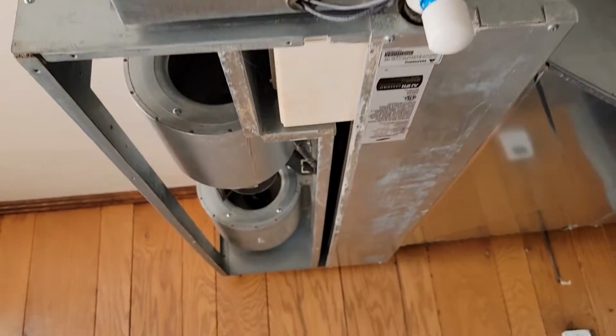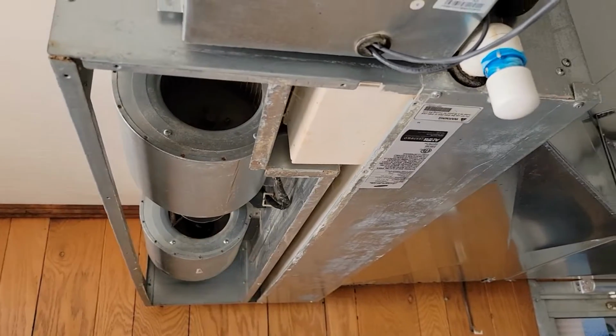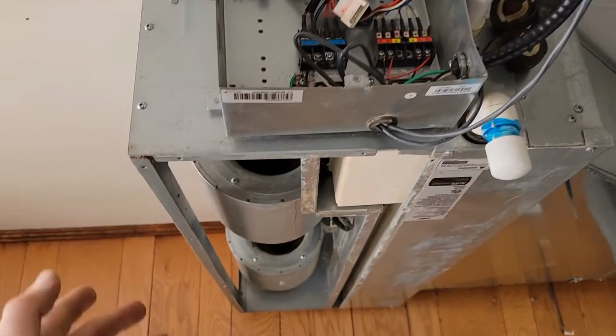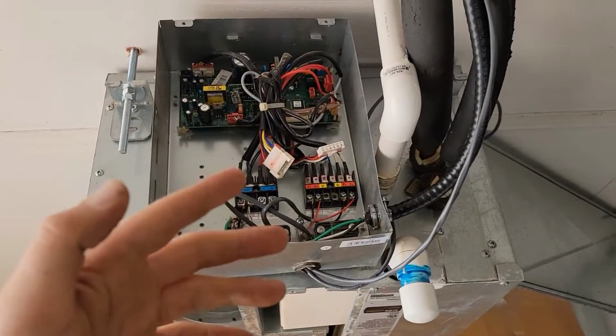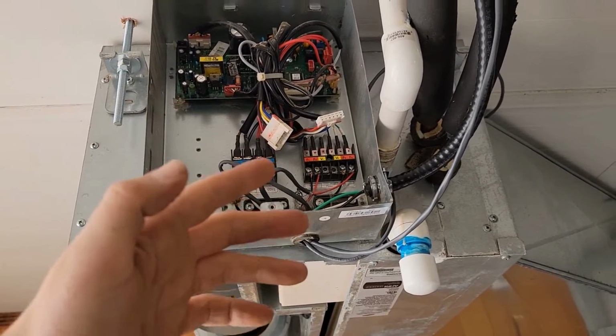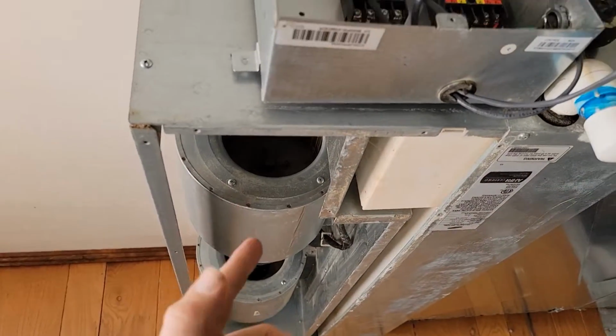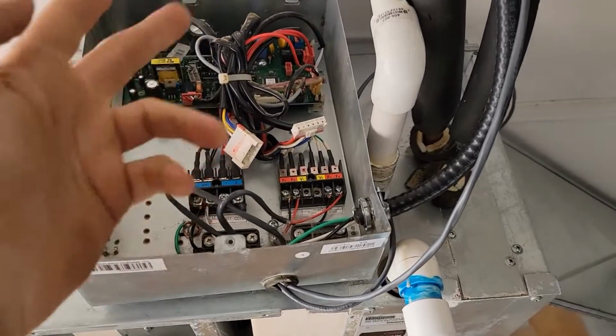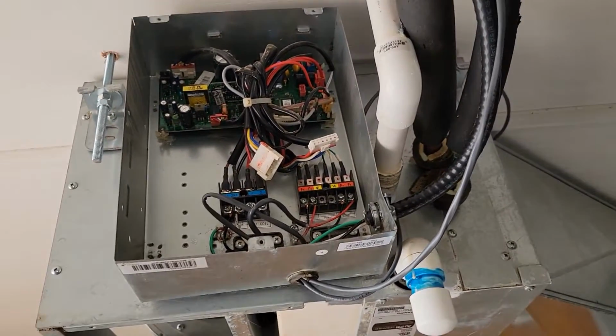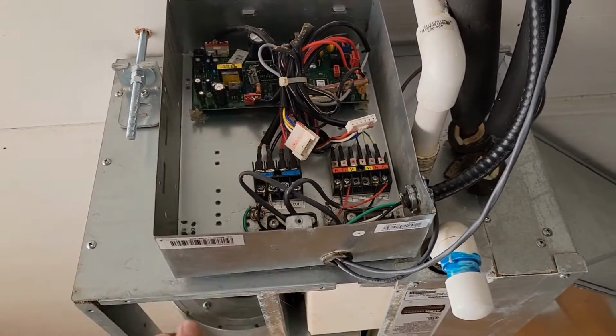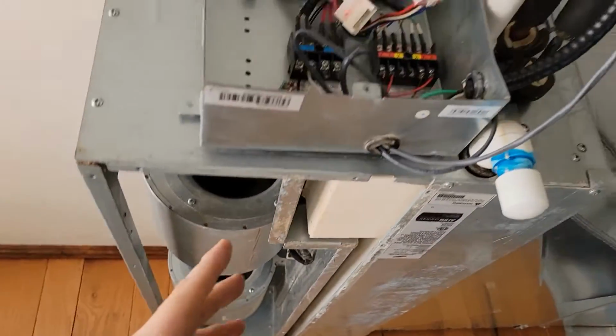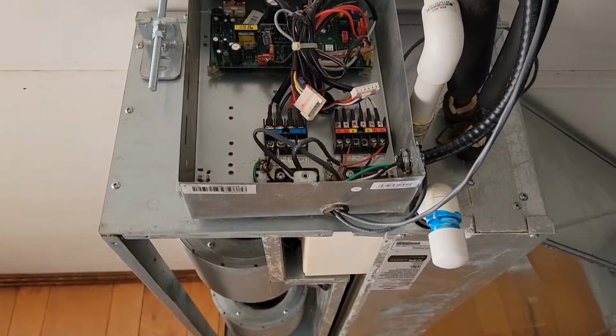But this is a fan error - it's got something to do with the indoor fan. It could be a matter of the motor being bad due to a couple reasons, something stuck in the wheels, or it's not plugged in. You could also have a bad board, but in my case I had a bad indoor fan motor, and we're going to go to some installation tips.